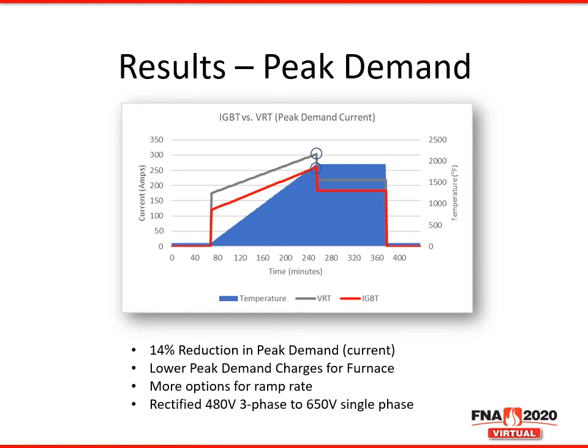Next, let's examine the peak demand, or the highest instantaneous current that's used for the process. This graph is similar to the last slide, where you have the heat treat cycle in blue in the soak phase at 1900 degrees Fahrenheit. The left y-axis is now amperage or current. Again, you can see the trend of increasing current during the ramp phase and then a plateau phase of energy requirement. Within the circles on the graph, you can see the peak current draw. We identified a 14% reduction from the VRT to the IGBT MFDC power supply. This correlates to lower peak demand charges for the furnace.